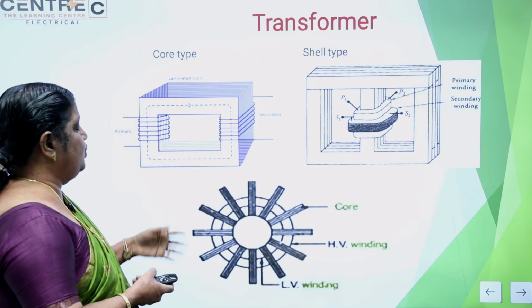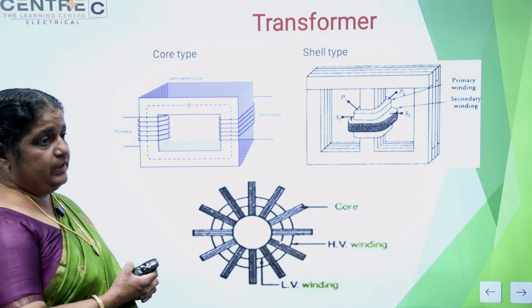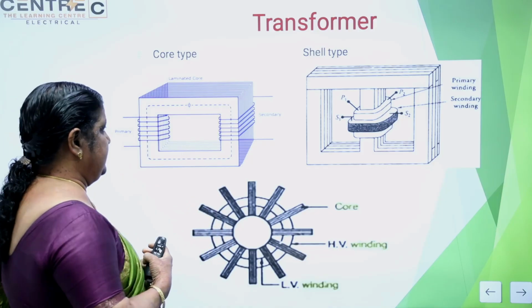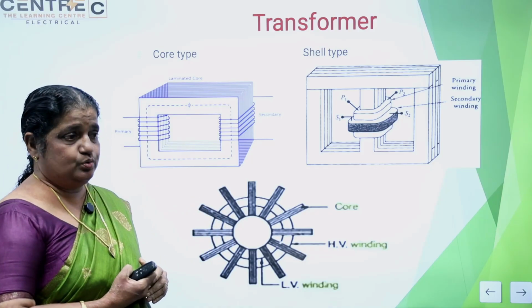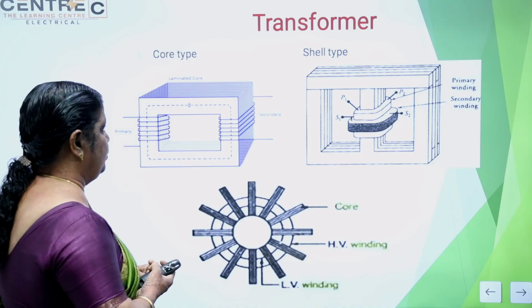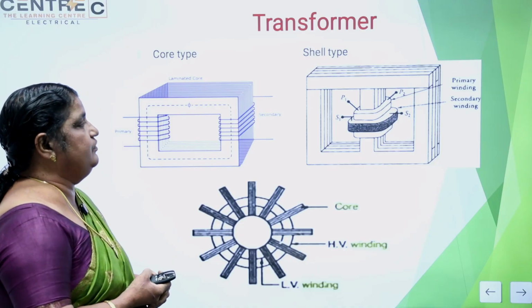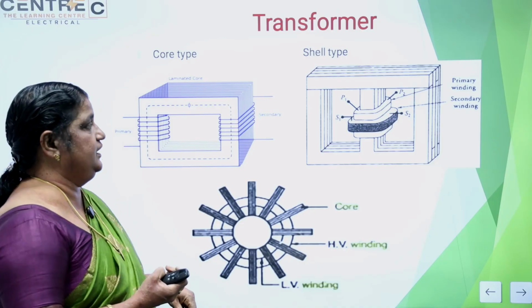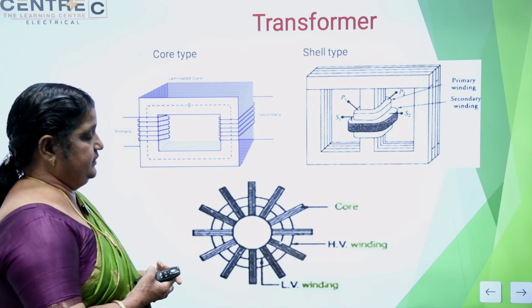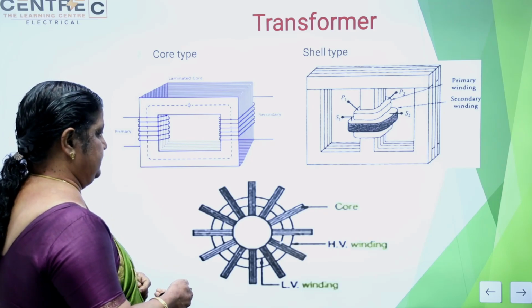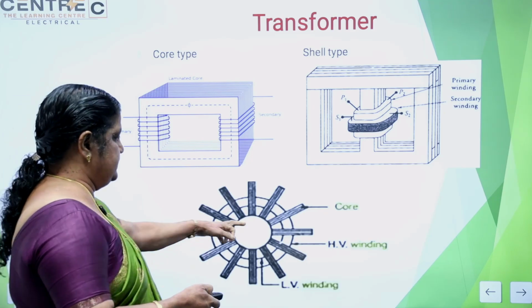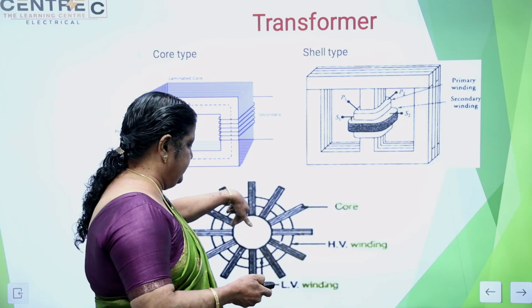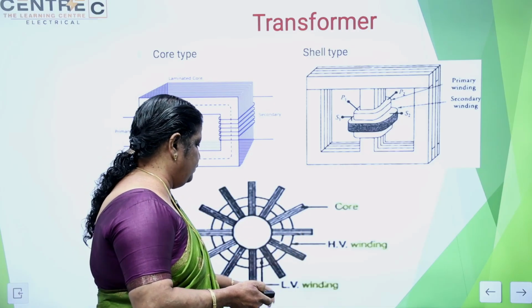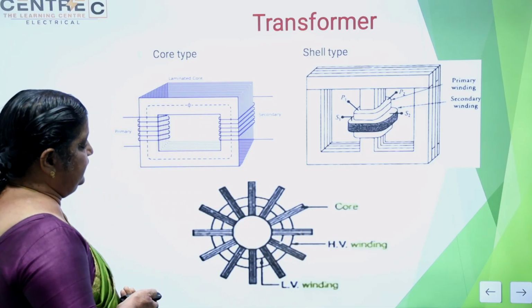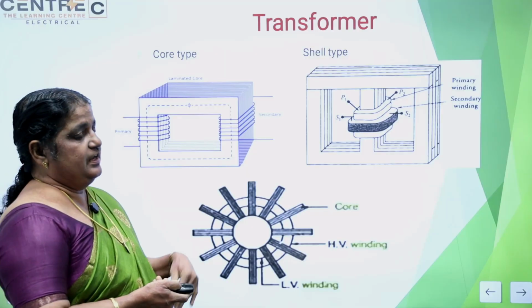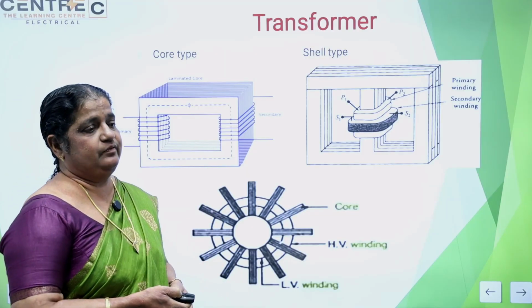Then this one is core type, that is, two limbs, and the windings are surrounded by the two limbs of the core. It is called core type. Then with the middle limb and winding, that is called shell type. Then the berry type is this one. Core is this one, winding is this one, cylindrical shape. Then low voltage winding and high voltage winding: the low voltage winding is inside, and the high voltage winding is outside.